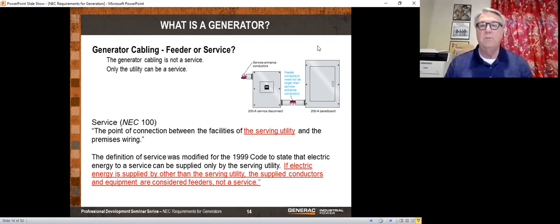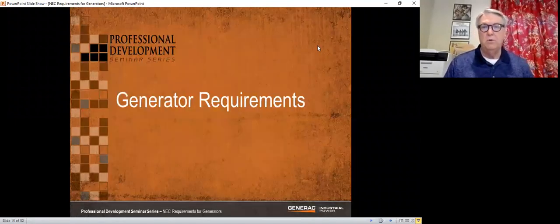The definition of service was modified in the 1999 code to state that electric energy to a service can be supplied only by the serving utility. If electric energy is supplied by other than a serving utility, the supplied conductors and equipment are considered feeders, not a service. So this is a common point of confusion. People say, well, the generator, that's just another service. That's another place to get electricity. Well, that may be true, but as far as the National Electrical Code goes, it is not a service. The service is strictly the connection to the utility, and anything having to do with the generator is going to be feeder rules, not service rules.